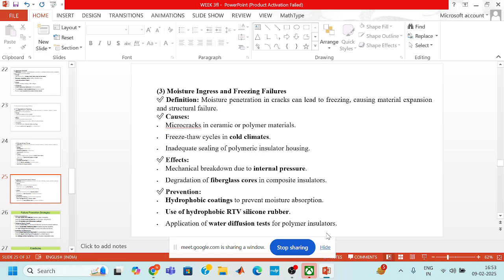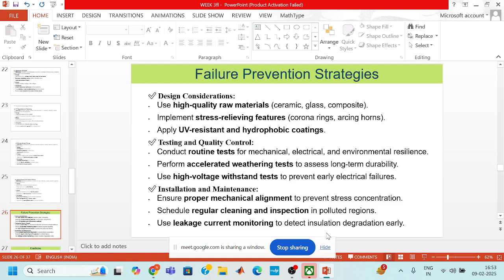Now, moisture ingress and freezing failures. Moisture penetration into cracks can lead to freezing, causing material expansion and structural failure. The causes are micro cracks in ceramic or polymer materials, freeze-thaw cycles in cold climates, and inadequate sealing of polymeric insulator housing. Due to this, mechanical breakdown occurs due to internal pressure and degradation of fiberglass cores in composite insulators. The main prevention is hydrophobic coatings to prevent moisture absorption, so we can use hydrophobic RTV silicone rubber, and apply water diffusion tests for polymer insulators.